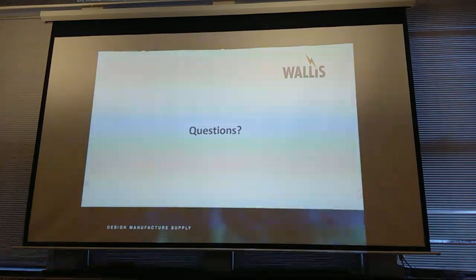I mean, we've had sites for IDNOs where they're on a long 11 kV run. I'm talking 5 kilometre 11 kV runs, and you've got 80% of the fault going to the general mass of earth because it's all clay and it's really, really good. So that's your lower impedance path rather than going up the cable sheath. So it's one of those that, unfortunately, it's not an easy, you shall do this each and every time. It does vary each and every job, each and every substation. It will be different. I can't give you a simple answer, sorry.